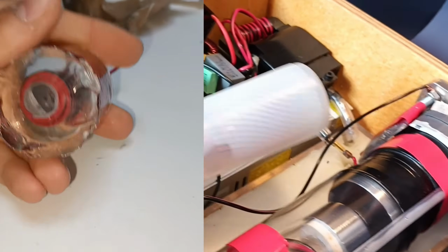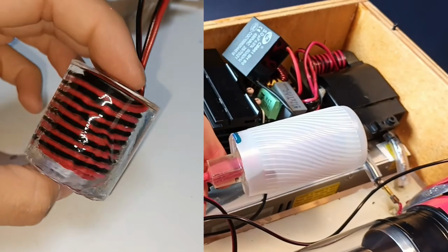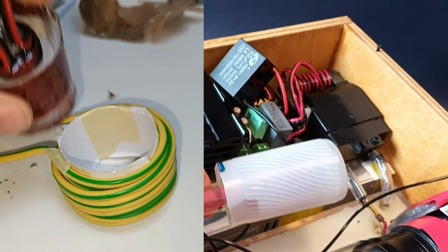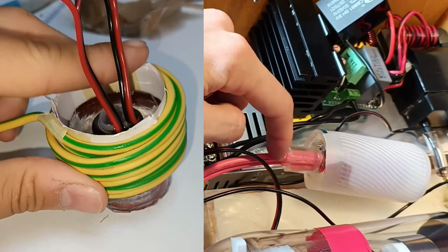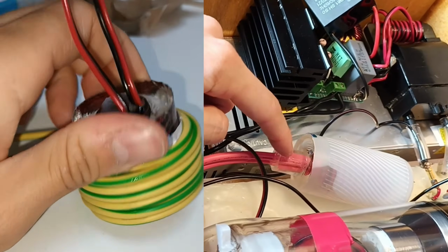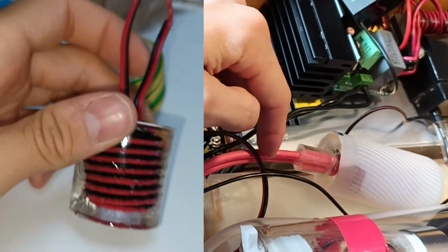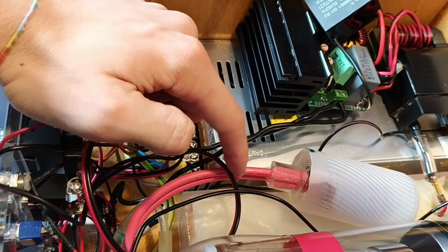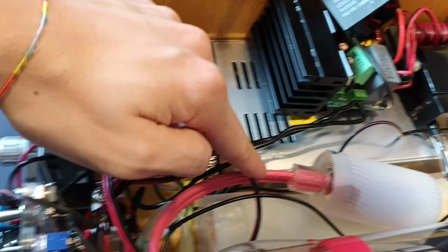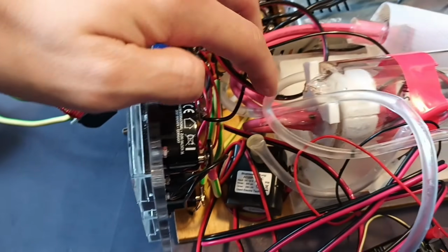The insulation is needed because when this tube is energized, inside of the bottle there's like 60,000 volts, so you don't want a short circuit to happen, and so the power that is fed to the filament flows through these 2 cables from the secondary coil to the high voltage feedthrough.